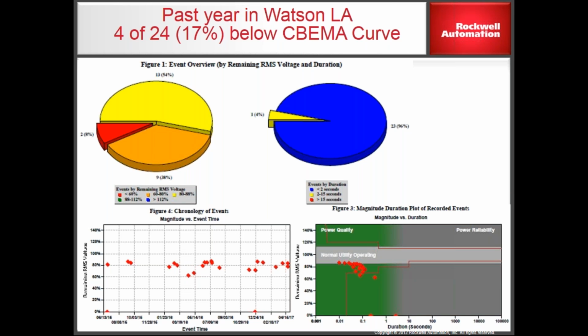As we look at how the data falls on our graph, we can start to understand what types of technology are needed to solve the problem. If all your problems are under 5 seconds, you've got 3 different technologies to choose from. If all your problems are way up in the outage area, you've only got one - really a combination: either a UPS to a generator, or a flywheel to a generator. That's it, if you're going to really solve those problems.